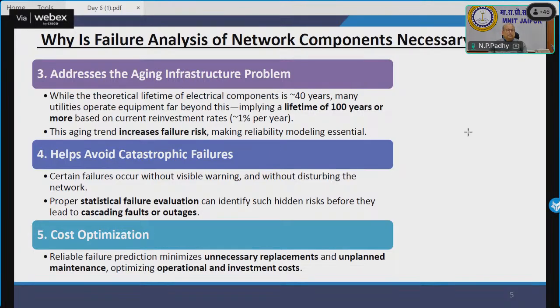The theoretical lifetime of an electrical component is close to 40 years, and normally every component needs to be changed after that. In many utilities, since independence, India might not have replaced 50% of the distribution assets installed at that time. So equipment operates well beyond its theoretical life, implying a lifetime of 100 years or more, based on a current reinvestment rate of only 1% per year. Many utilities utilize equipment for even up to 100 years. If you look at a generating plant, it may have been running for 80 to 90 years.